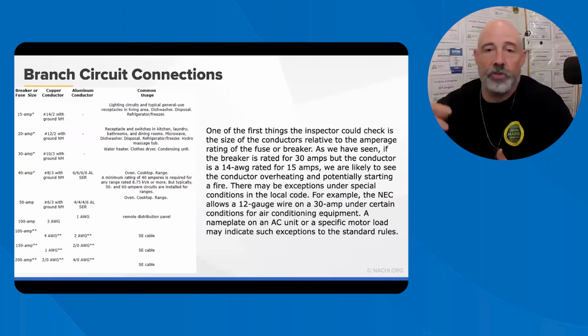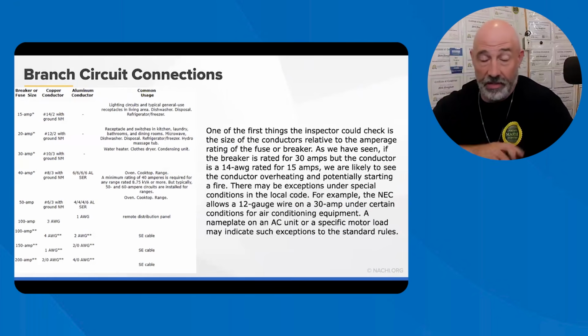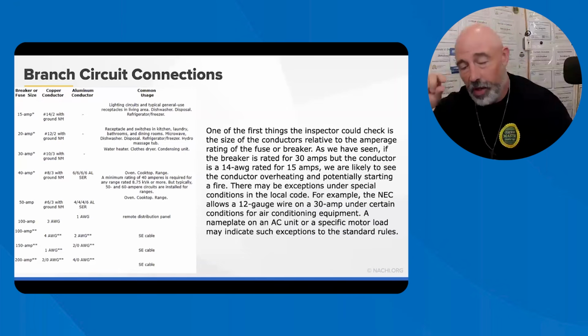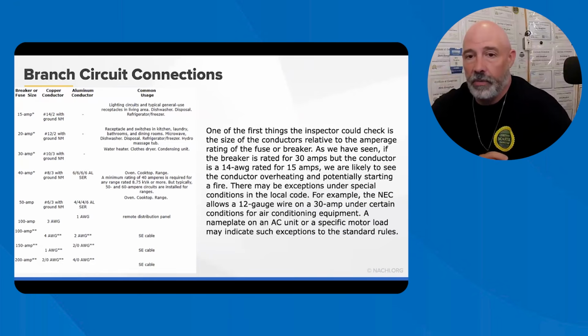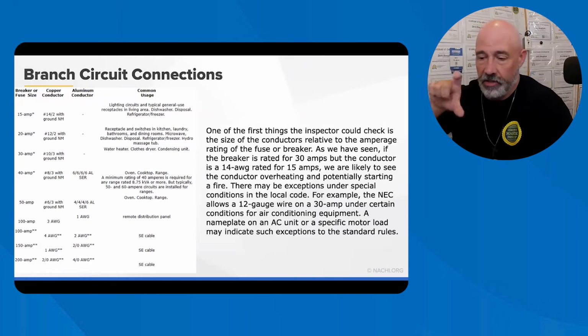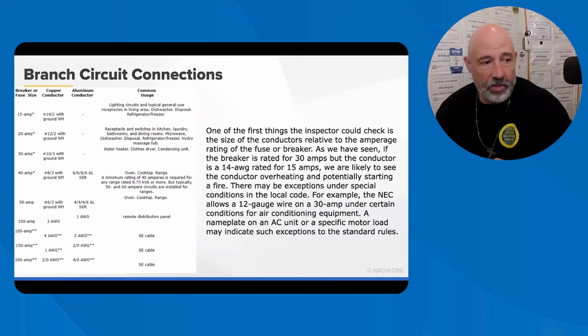One of the first things inspectors should really check is whether the breaker size matches the conductor size. Like I said, I start with the 15 amp breaker and the 14 gauge wire. That wire is the thinnest one most of the time, and then you gauge it from there. You can always go to a hardware store and get one of those plastic gauges, and you can see what the gauge size is if you're really unsure of that. So there are some things that you can actually do.